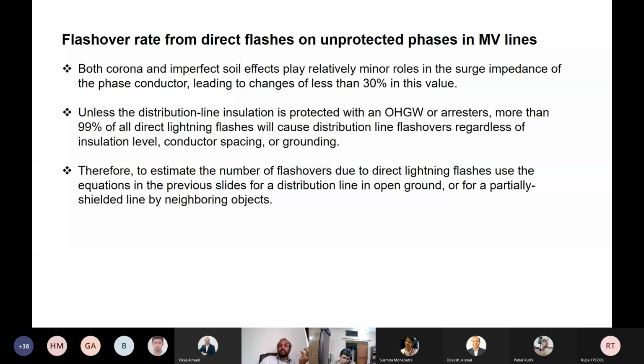Therefore, to estimate the number of flashovers due to direct lightning flashes, use the equations in the previous slides for a distribution line in open ground or for a partially shielded line by neighboring objects. It's very important that before you decide what type or level of protection should be given to a system, you consider the number of flashes that will be collected by the distribution line per 100 kilometers per year. This is the standard parameter.